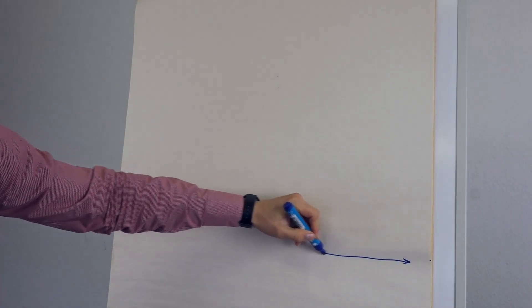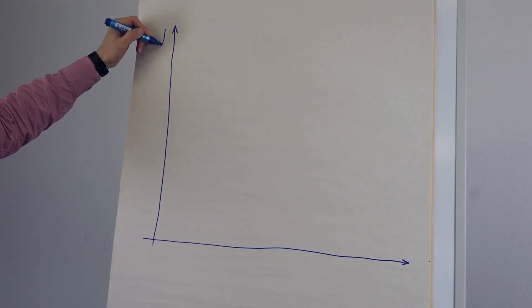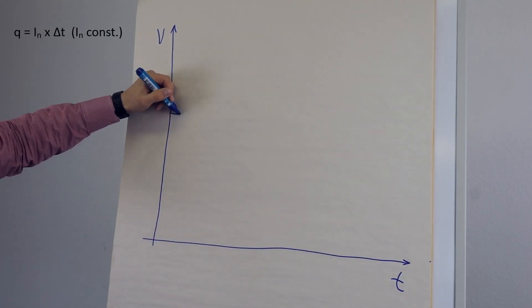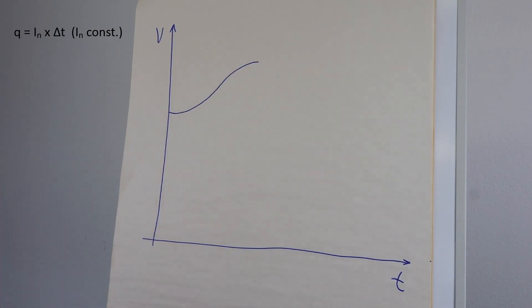In this case, we will monitor a full charge and discharge cycle of a nickel-cadmium battery. NiCad batteries are charged with constant current while the voltage increases freely. The charging happens at a rate expressed as a fraction of the battery's nominal current, defined as the current that can fully charge the battery in one hour. Usually, charging rates of 10 up to 100% of the nominal current are applied.